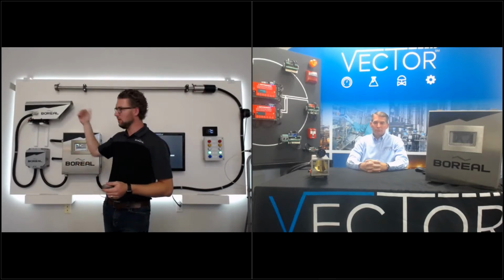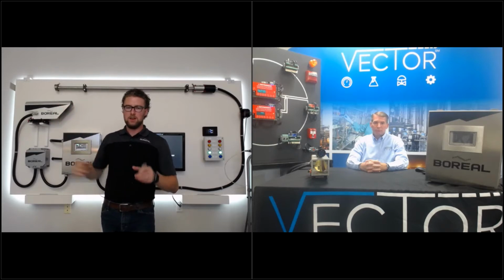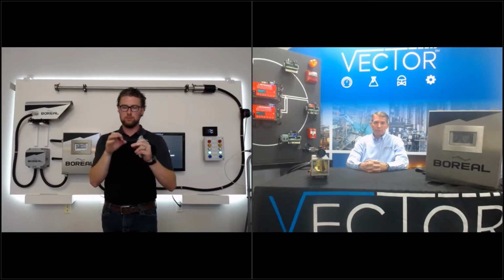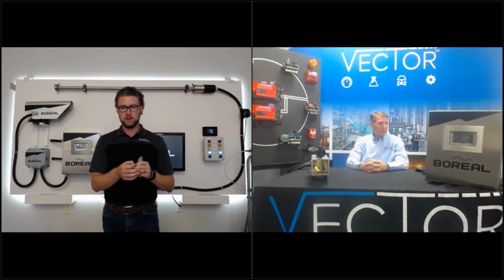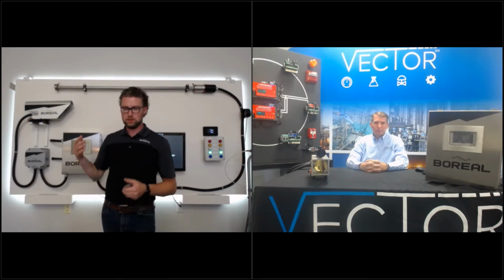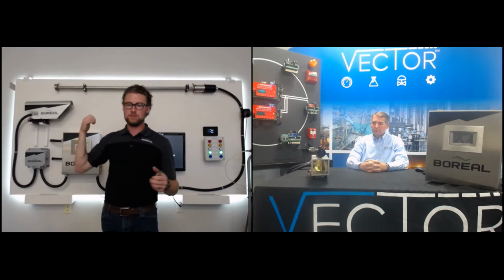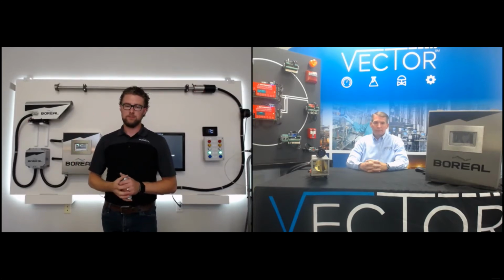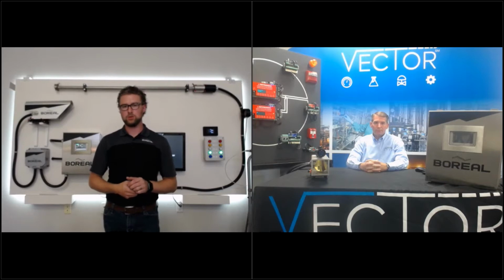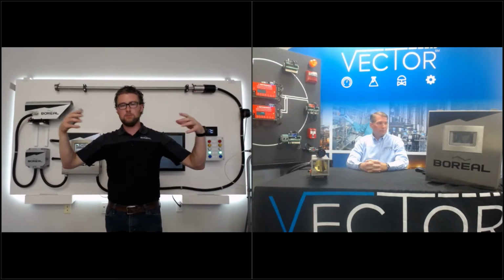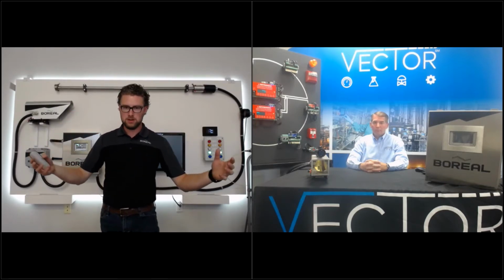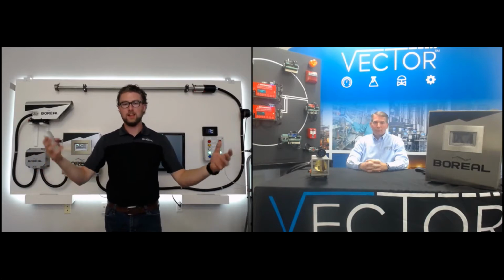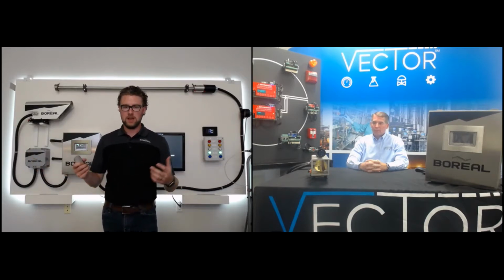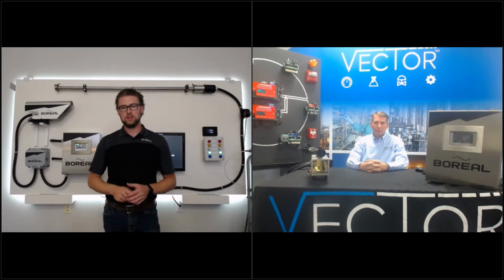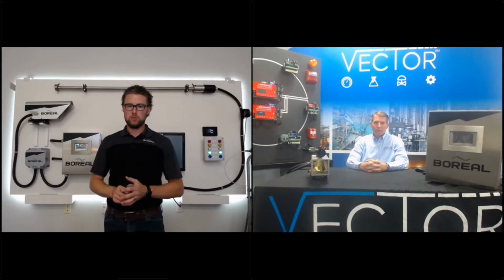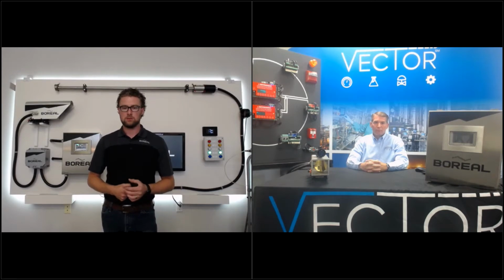So the line of sight measurements that we have here enable much, much larger area coverage compared to the 1-inch contact surface area. We have much faster speed of response, with one independent sample every single second. And often we have very, very low detection thresholds that we can alarm. If it's a combustible gas, we can alarm in percent concentrations. Think LEL or LFL meter applications. Or in the case of toxic gases, we can see sub ppm concentrations for these arrangements as well.